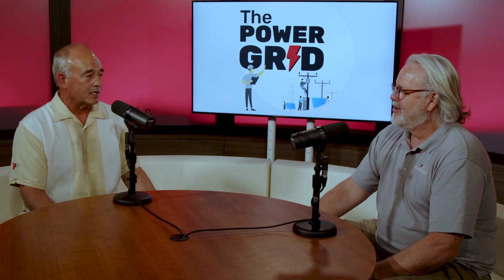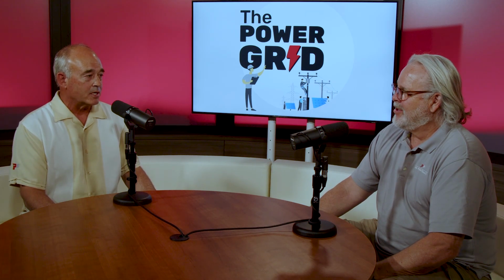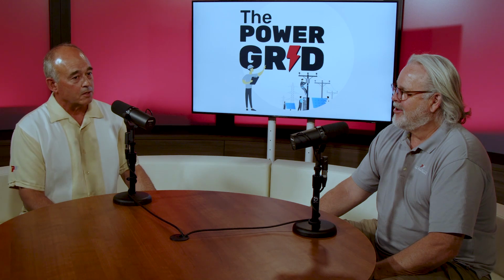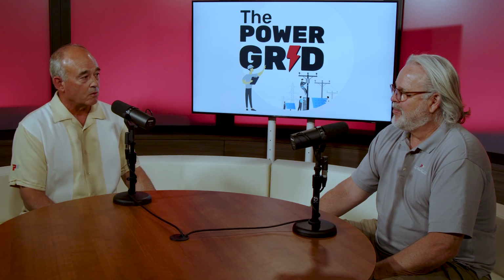Sure. So it's always a good idea, if you have data communications running between those, to look at dedicated surge protection for the data stream you're trying to protect. Okay, so like 4 to 20 milliamp signal loops? Anything like that. Water treatment facilities are a perfect example. We can put electrical protection on the main service. We can put it on the motor control center that feeds all these huge pumps out at their wells. Yet they have 4 to 20 milliamp circuit loops out there that report directly back into what we're trying to protect, and they can get hit by lightning, and they do all the time.